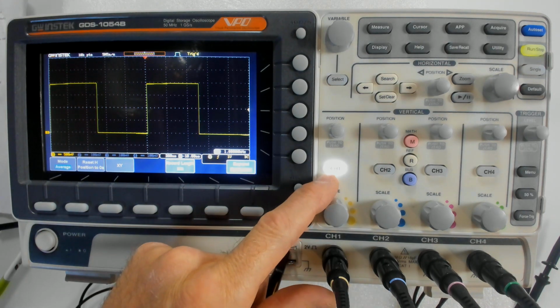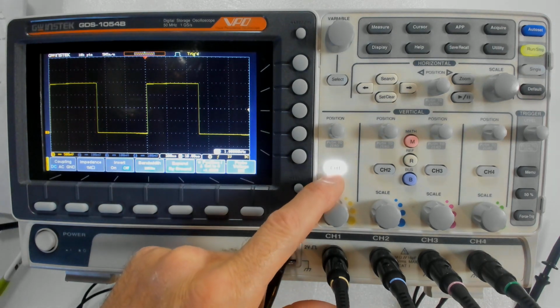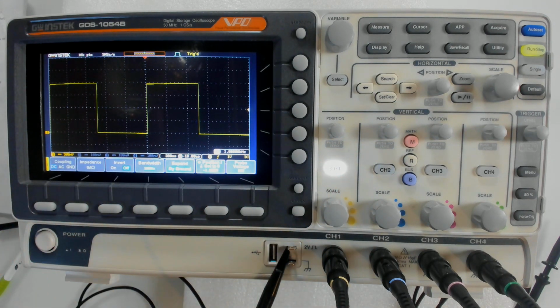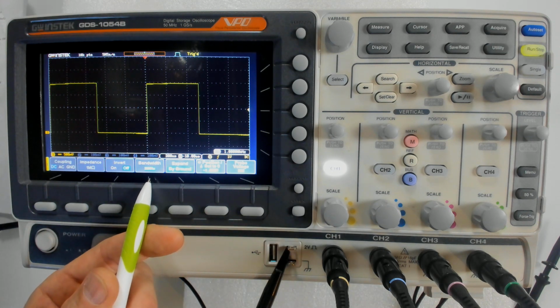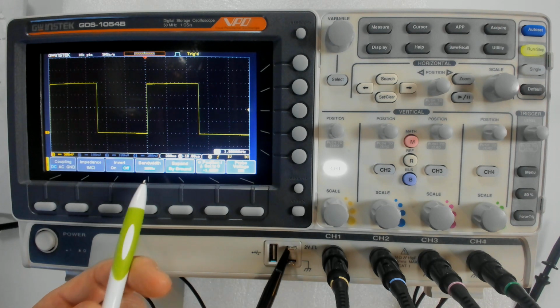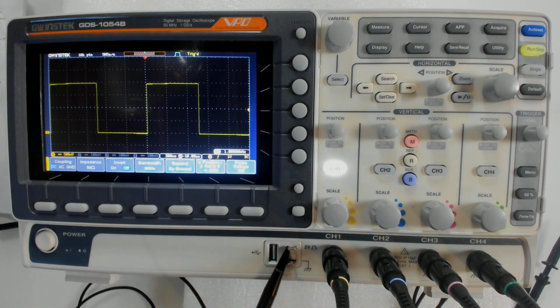Don't forget, in channel 1's menu, I'm just going to hit the channel button, and when I hit channel 1, it brings up this menu. The other thing that helps us get nice clean lines, a little bit, is this bandwidth limit. Remember, we threw away everything above 20 megahertz because we're not really interested in measuring anything above that. We're way below 20 megahertz. So that's what the bandwidth limit did for us. So that's another way to help clean up waveforms. It gets rid of noise above 20 megahertz, which we don't care about anyway. We don't want to see that signal. And then the averaging is the other thing that got rid of noise, a little bit falsely. I mean, it's there, but we just averaged it out.